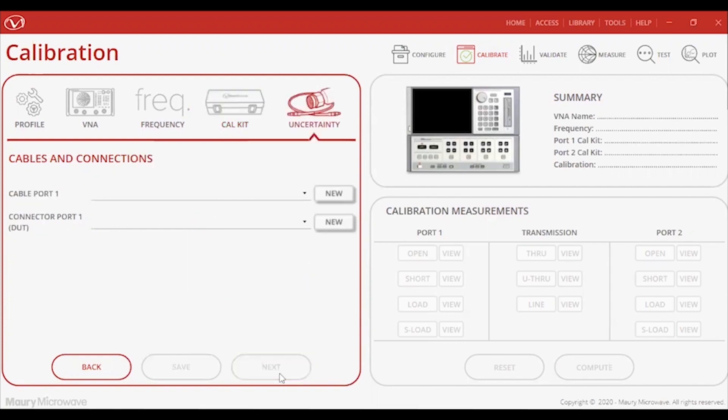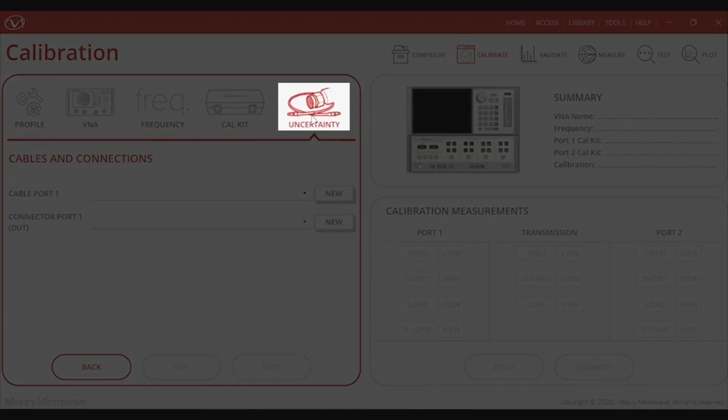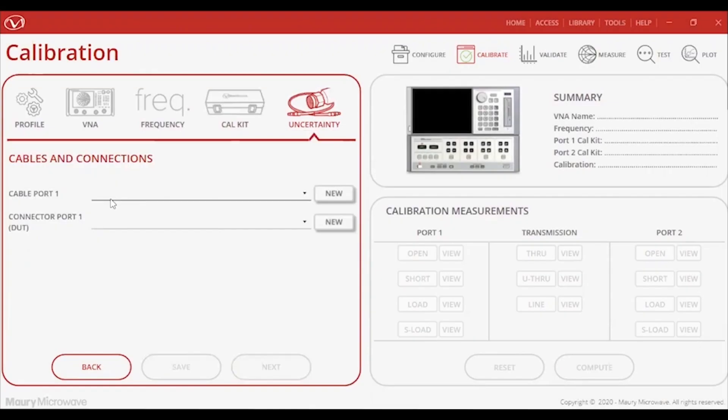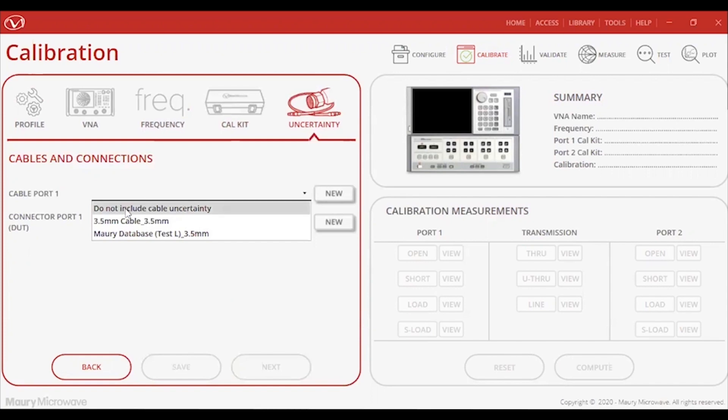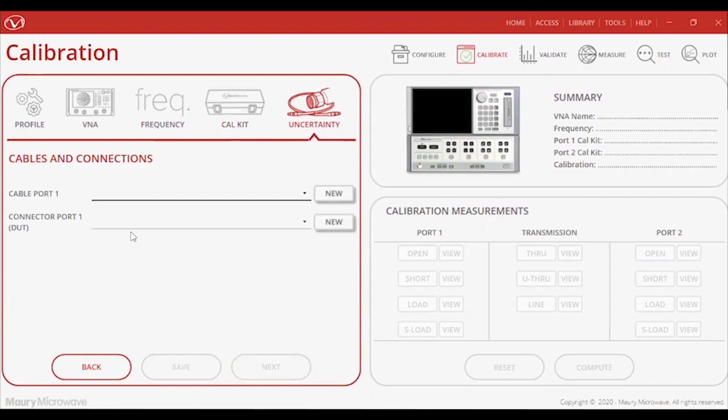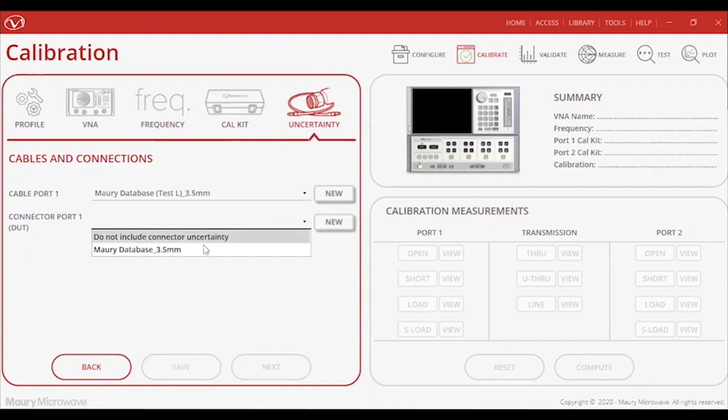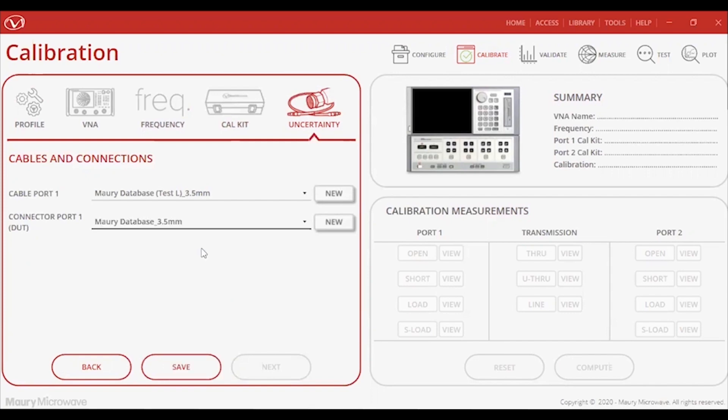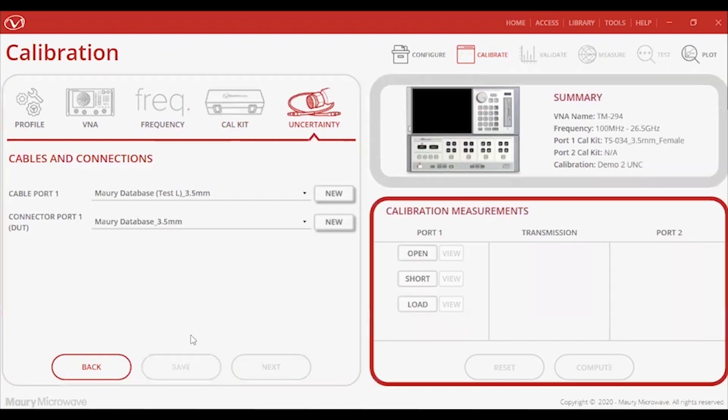Once my calibration method is set, I can proceed on to setting up the cable and connector uncertainties in the next tab. I'll go ahead and load the uncertainty files created from the previous module to add to the total uncertainty budget. Remember, this is an optional step, but it does add a lot of insight into your measurements and can help increase your confidence in taking those measurements. And that's it as far as dialing in your calibration settings.